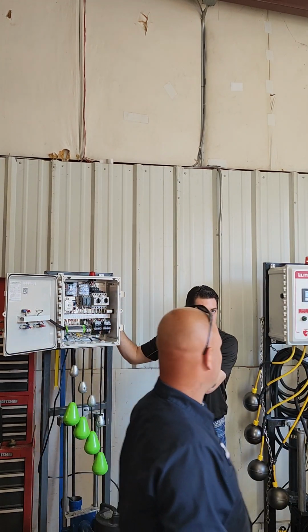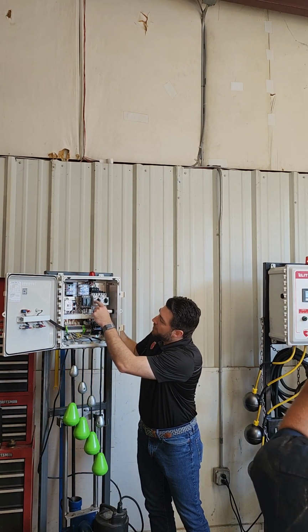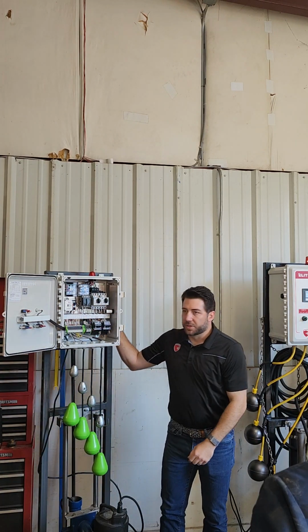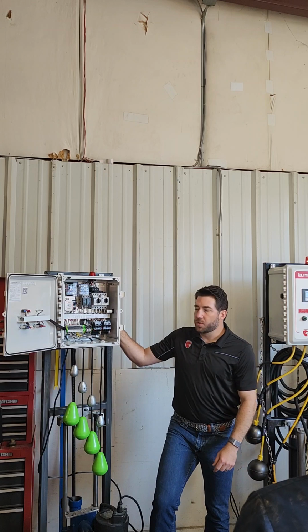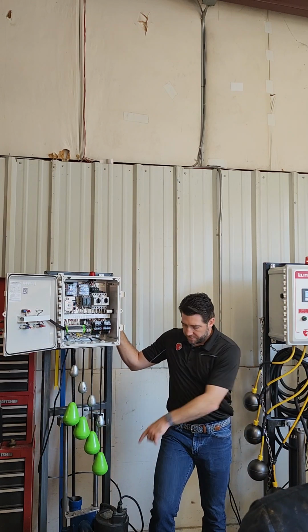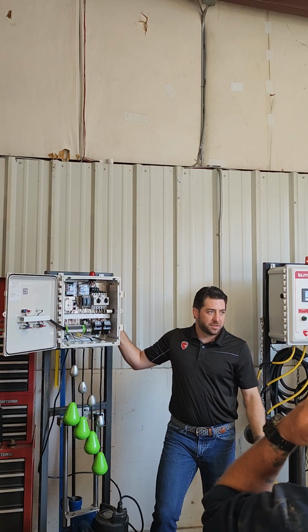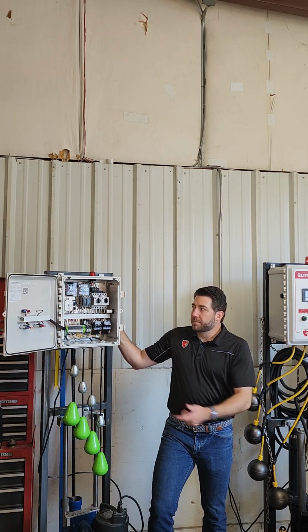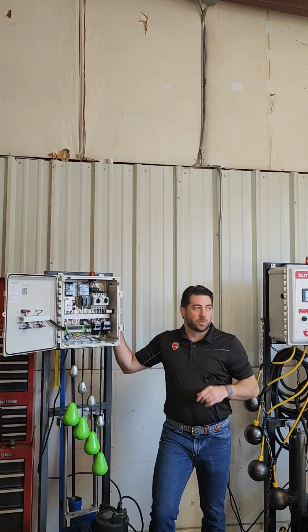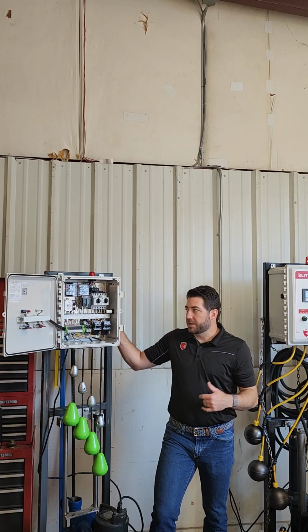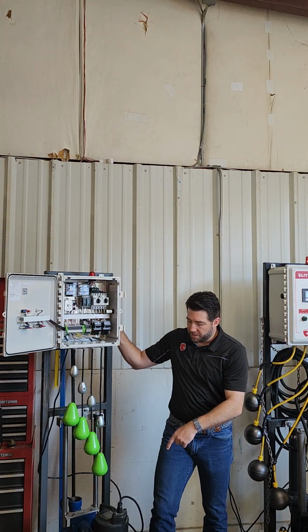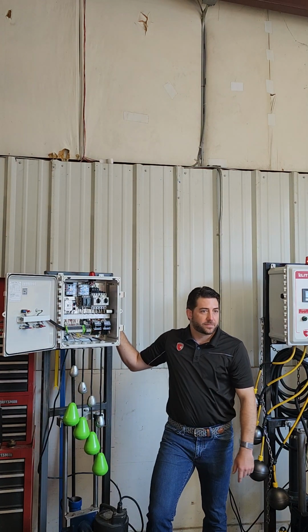Mine straight on the side. Yeah. Thank you. Right up here. So if you want it dialed into whatever it is on the nameplate, otherwise it's either not going to trip or it's going to trip too early. But if it's tripping immediately when you try to run the pump, that's probably an indication of a direct short, so either inside the motor or in the wiring.